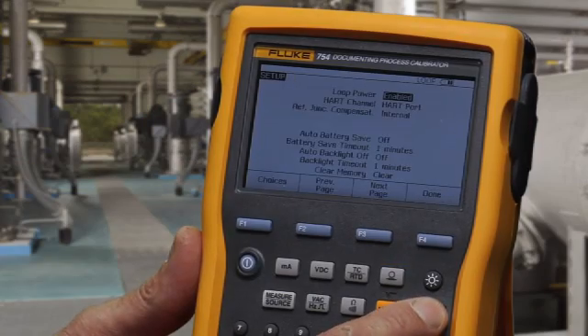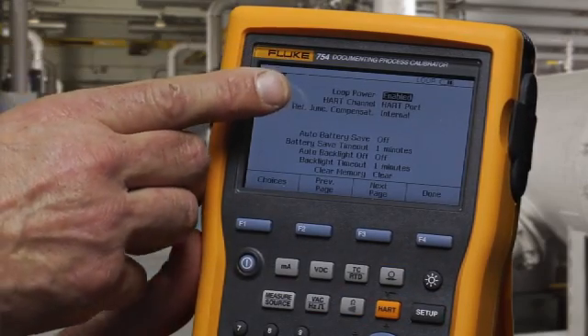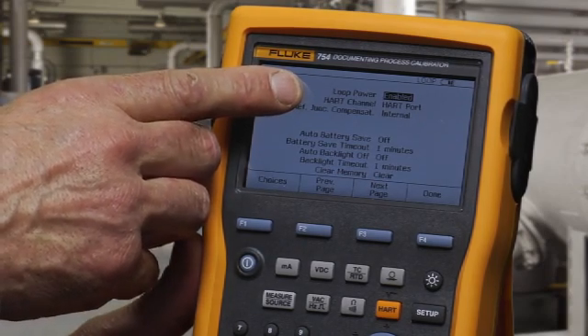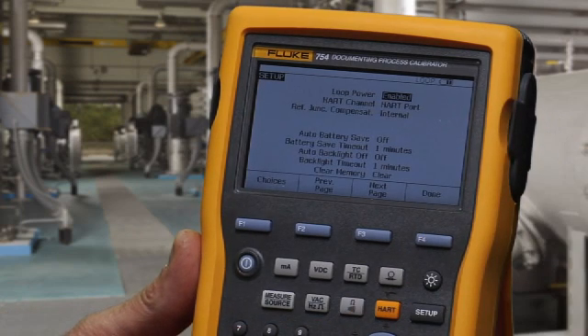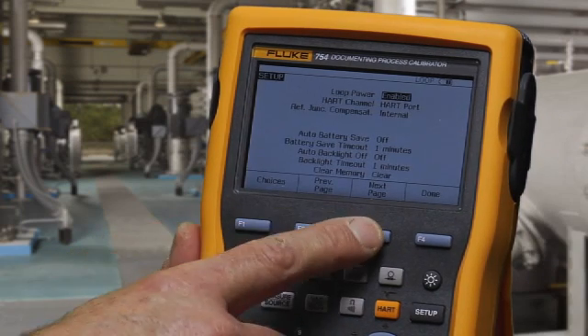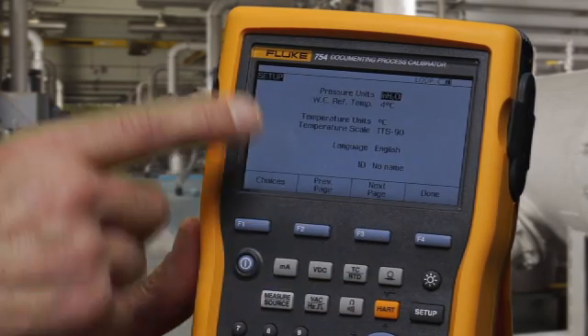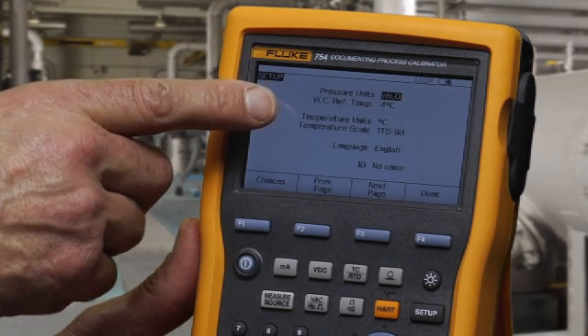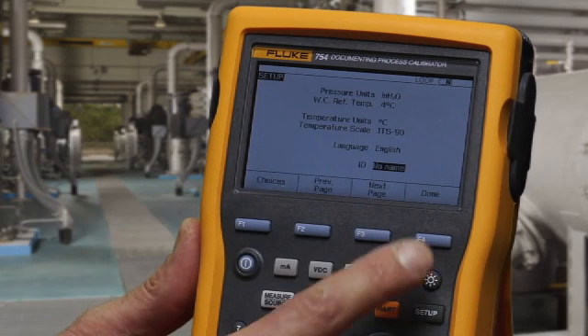In the set-up screen, we can configure and turn on loop power. We can change the direction of the HART communication signal from the digital connector on the side to the milliamp measurement ports. We can also set the time and the date, select pressure units, change pressure units and temperature units, and put our name into the calibrator to personalize it.